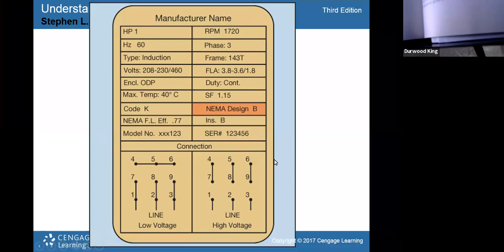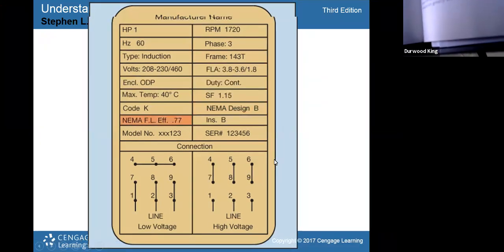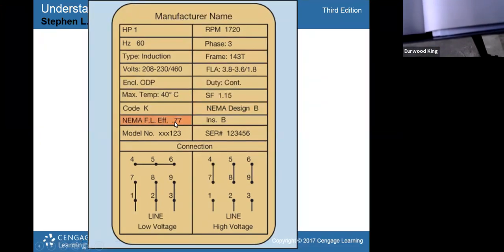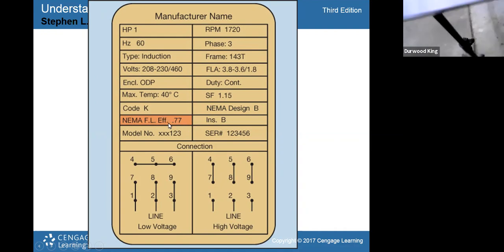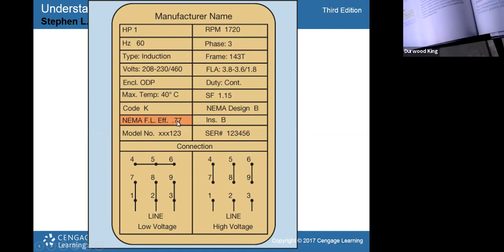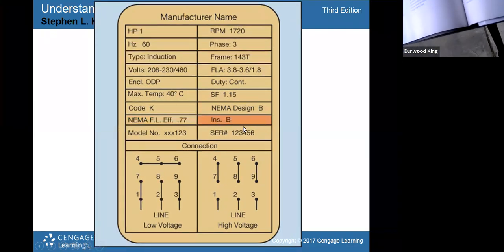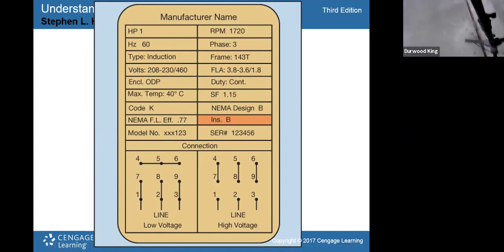Go back to center. So that's efficiency, EFF, and that has a 0.77 efficiency rating there. And then the insulation, INS, would be insulation. That's going to be on your temperature rating of the motor, how hot of an environment it can handle. So your information for that would be right here.